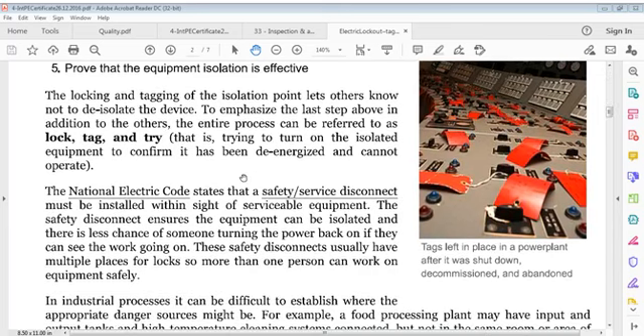So let's go. Locking and tagging of an isolation point lets others know not to de-isolate the device. To emphasize the last step above in addition to the others, the entire process can be referred to as lock, tag and try. That is, try to turn on the isolated equipment to confirm it has been de-energized and cannot operate.